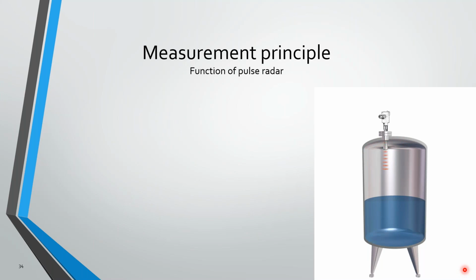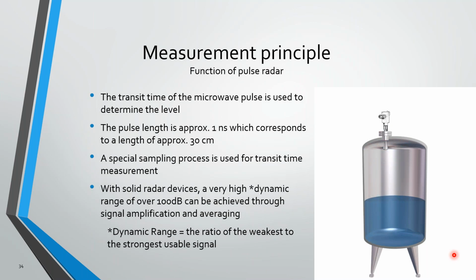So the function of pulse radar: you notice we send a signal down, we wait for it to come back. If you're watching the bottom right side of the screen here, the transit time of the pulse is used to determine the level. Again, a 1 nanosecond pulse is roughly 30 centimeters. We can get a pretty high dynamic range with these devices, and dynamic range is the ratio of the weakest to the strongest usable signal. If you were looking at a flow device, you might relate this to turn down ratio, except we don't call it turn down ratio here, we call it the dynamic range of the instrument. We can get a spread of about 100 decibels.